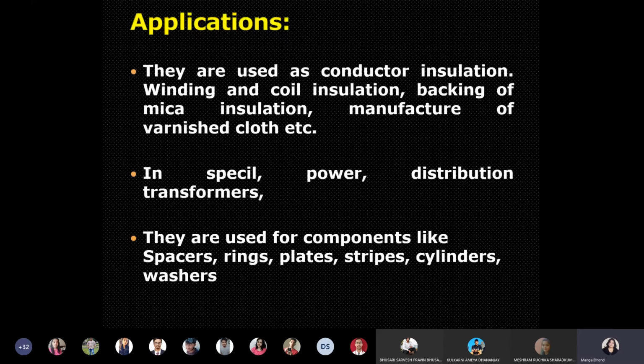So you will see the spacers, how the distance between the two overhead transmission lines is maintained. The same type of concept is used in transformer windings also, to maintain some distance between winding and winding, or between two parts. So spacers you can make with pressboard. Just add one piece of pressboard and you can maintain the desired distance between the two parts. Then pressboard is also used in rings, plates, stripes, cylinders, washers. So that way you can see the pictures.